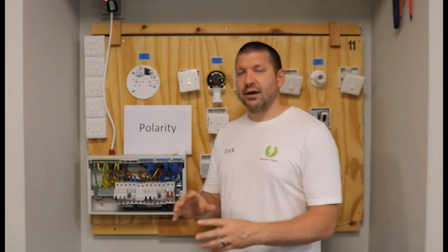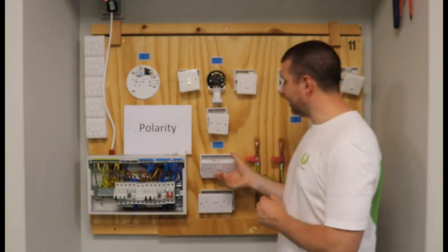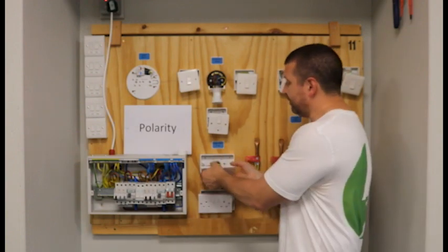Polarity test C simply says are the live cables, the brown cables going into the live connection and are the neutral cables going into the neutral connections and the earth cables into the earth cables. So that's a visual check.